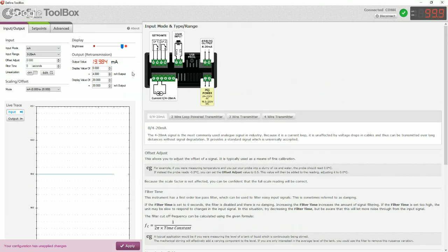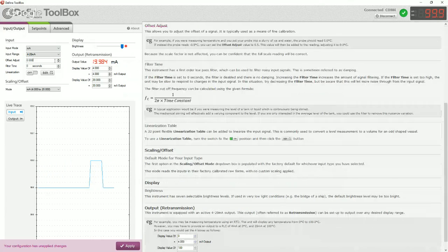So we're all ready to go. That's your wiring diagram there, which is available for you later on. So input range, our sensor is a 4 to 20 milliamp sensor. We can adjust the offset, so if there was a bit of error in the probe, we could get rid of that. There's also filter time. We're not going to need that in this application.